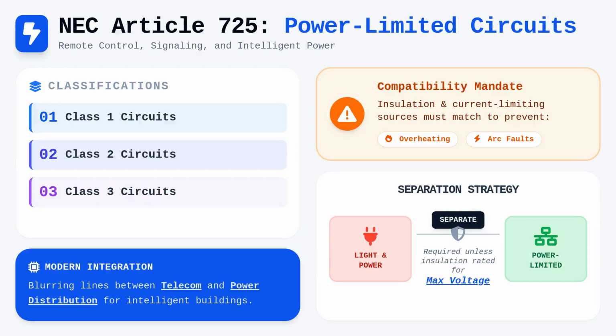These circuits must be separated from light and power circuits unless the insulation of the power-limited circuit is rated for the maximum voltage that could be present. Proper separation maintains the integrity of the data stream and prevents power surges from migrating into your communications equipment.